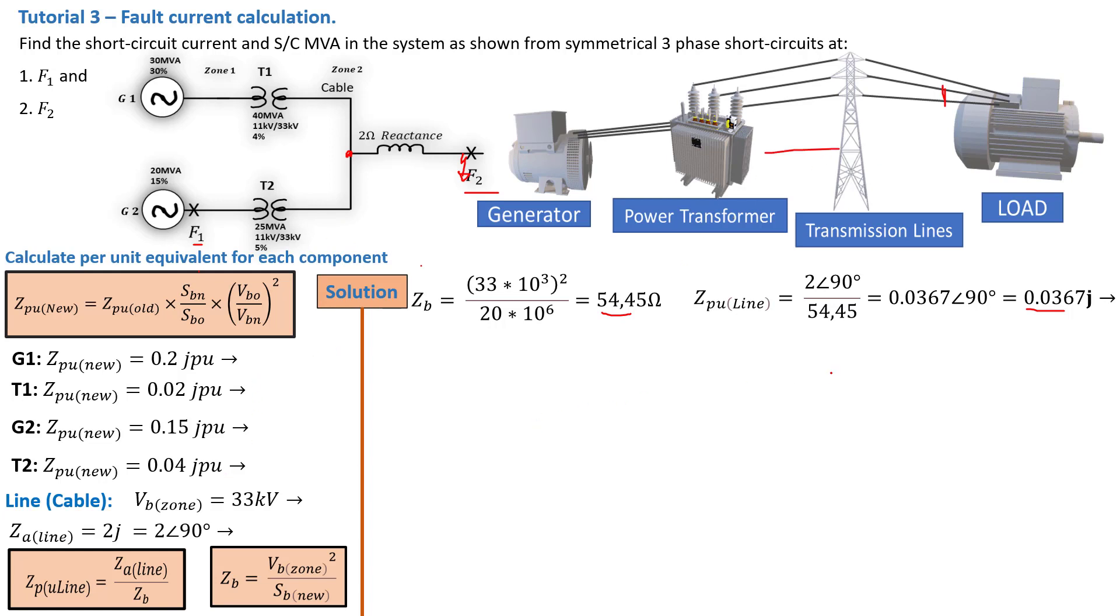Now at this point, what you've done so far is you've converted this network here into a per unit network, an equivalent per unit impedance diagram. So you then need to redraw your circuit. That will be simply by replacing each one of these components with the equivalent per unit that you've just calculated. So G1 will be represented by 0.2 per unit, and G2, T1, and T2 as we've calculated. Your line will also be represented by the value that we've calculated there.